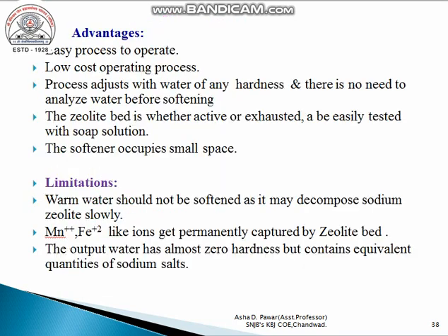So the zeolite process is a very simple process, and it has some advantages as well as some limitations. First of all, advantages: it is a very easy process to operate, with a low cost of operation, that is, only NaCl solution, the brine solution, is required for the regeneration of the bed again and again. The process adjusts to water of any hardness, and there is no need to analyze water before softening. That is, any hardness of water can be softened by using the zeolite bed.